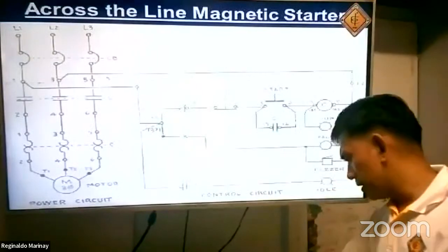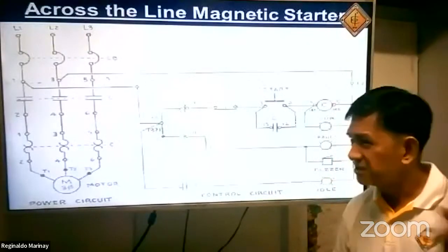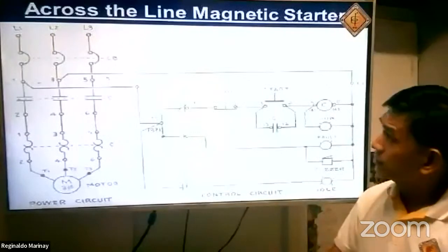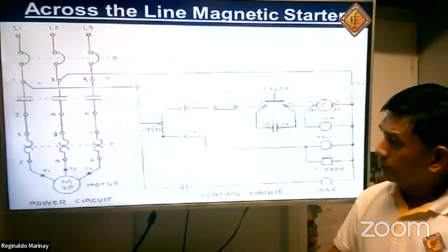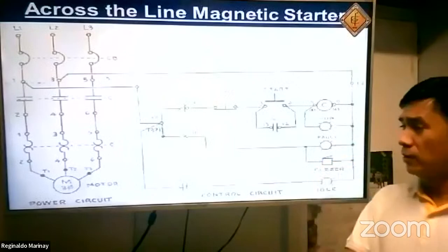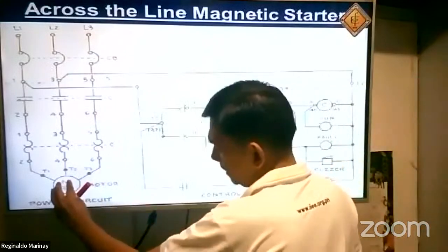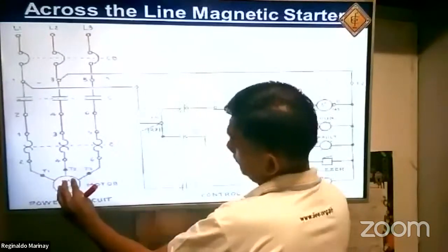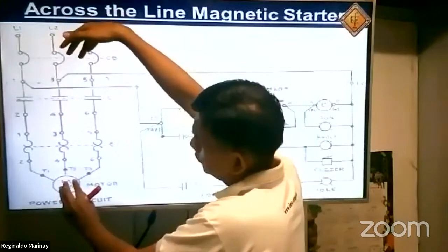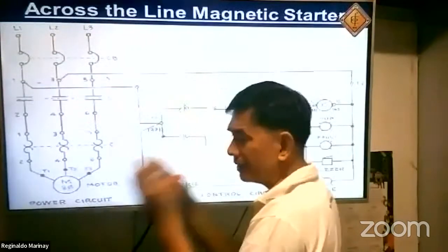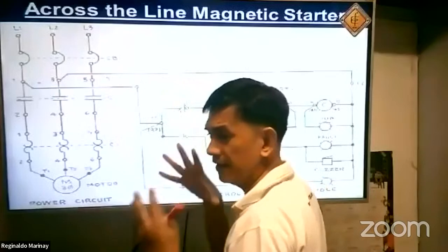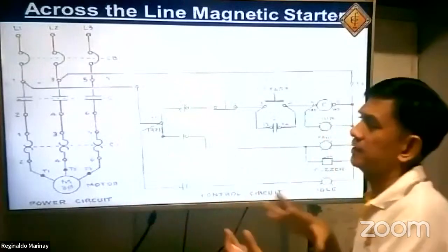That is across the line magnetic starter. Usually being used for low voltage, usually 600 volts and below, the across the line or full voltage. Why is it called a full voltage magnetic starter? Because with your motor, if you have 230 volts, you will start your motor right away at 230 volts. The voltage is full already right away.